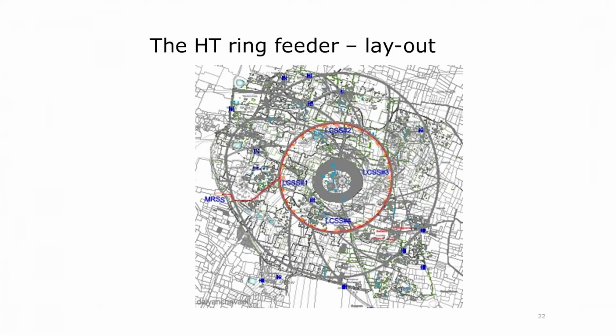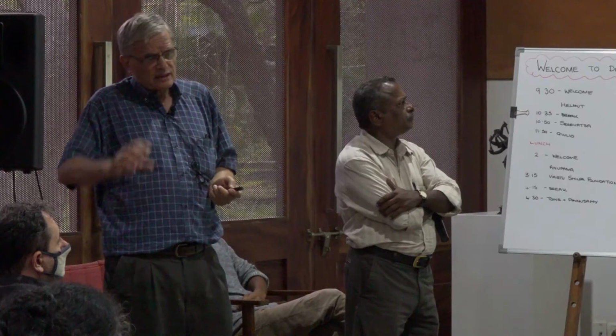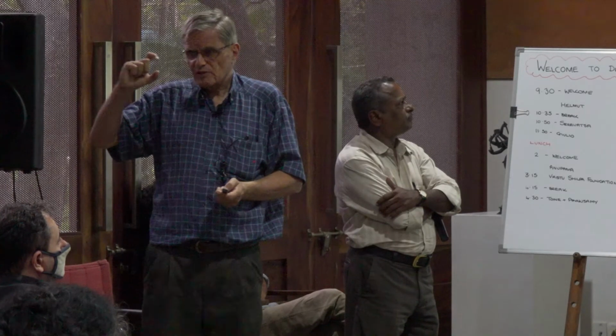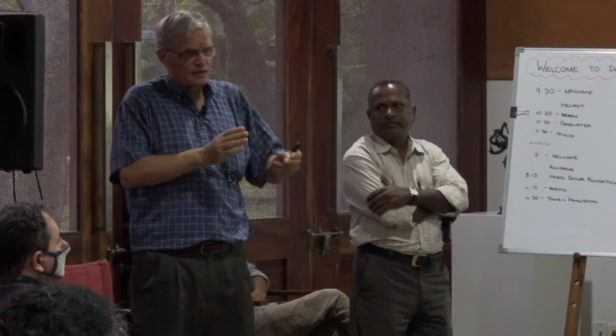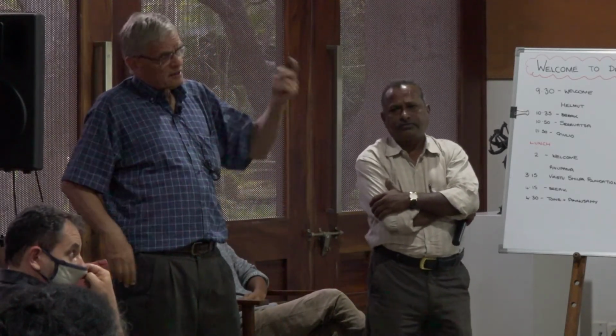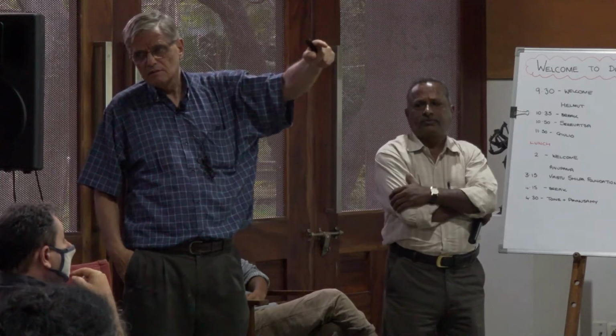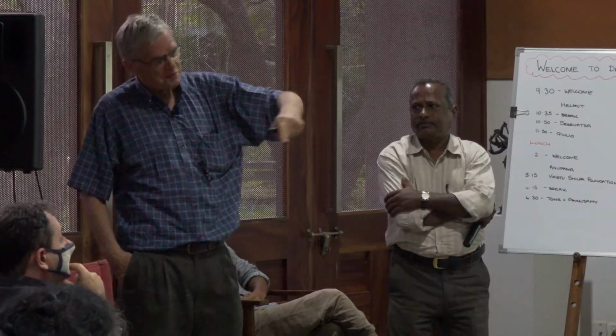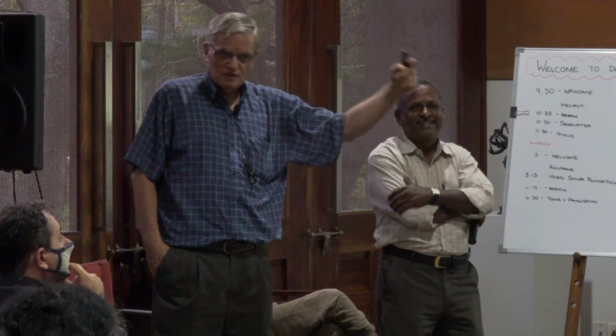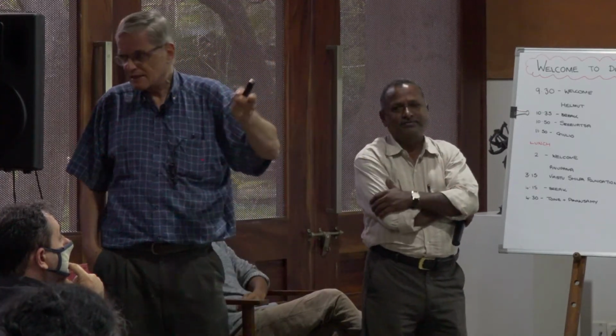Basically, the main features of the electrical plan: there is a high tension ring, which will be 11 kilovolt. For now it is 22. It has a total cross section of 600 square millimeter aluminium, but we are doing it in 2 steps. Right now one cable of 300 square mm is almost laid on one side of the crown, and the other will be laid later.